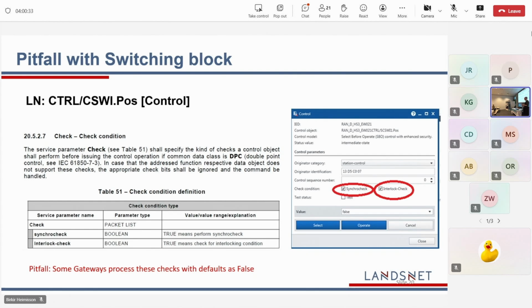So we immediately realized that. We managed to go on site and do outage-less maintenance to really test this out. Again, used the test philosophy to just test it while being in full operation. And then we changed the settings in the gateway to not inherit this from the 104, just always leave it on, and then it worked perfectly.